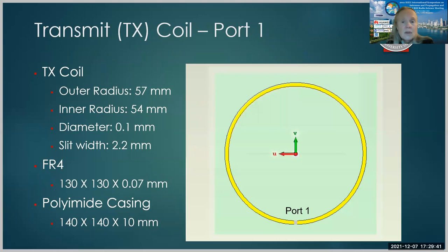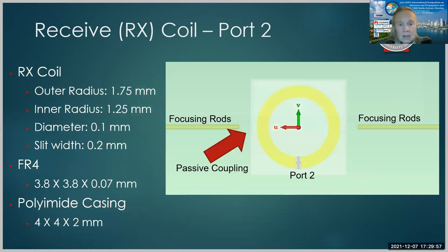So let's first look at the transmit and receiver coils. The transmit coil is a relatively large coil outside the body. It's produced on FR4, and it has a polyimide casing. All of this is simulated at this point. And then we have a receiver coil that's much smaller that could be on the four millimeter implant. And then if we are considering focusing rods, as we will in some of our cases, the focusing rods are not actually touching the internal antenna. They're just getting close to it. So there's passive coupling between the rods and the internal antenna, the receiver coil.